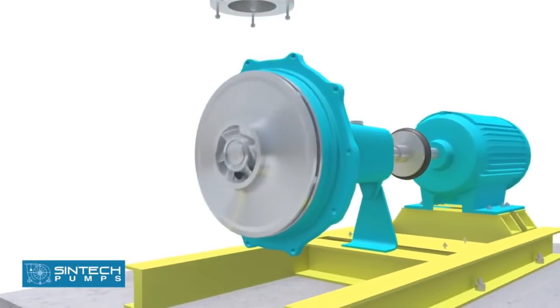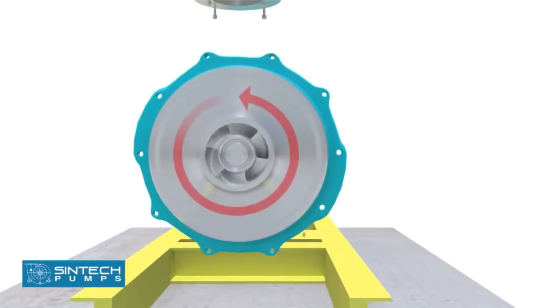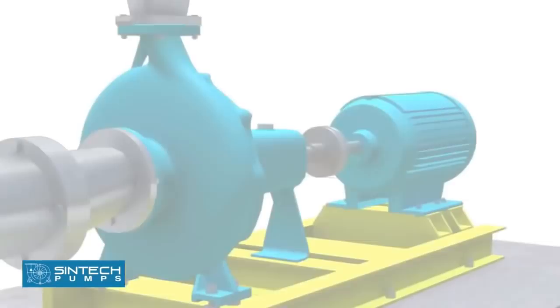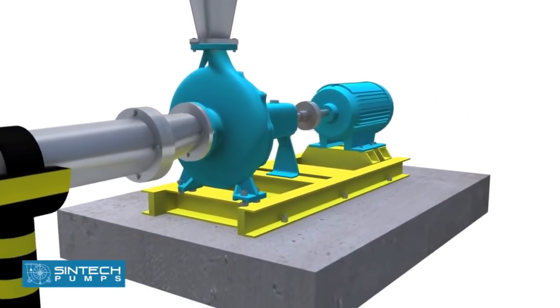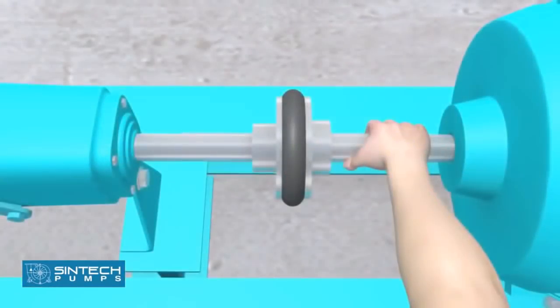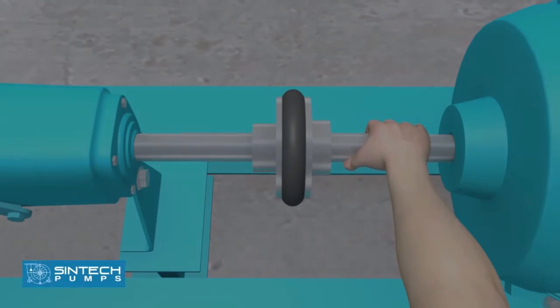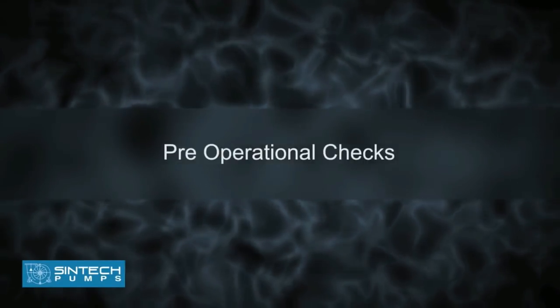The motor should be wired correctly to ensure the correct direction of rotation. This check has to be carried out before the pump is coupled. Once the pump and motor have been coupled, test the movement manually by rotating it by hand to see if the pump is rotating smoothly.